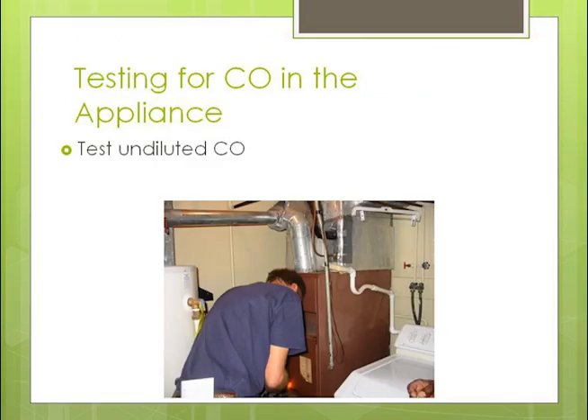There are a couple more slides about testing for carbon monoxide. This is a 70% furnace — you can tell because it's so old and because you can see through and see the flame. It's 70% because the person is sticking the carbon monoxide detector right into the flame, right into where the off-gases are starting to form.